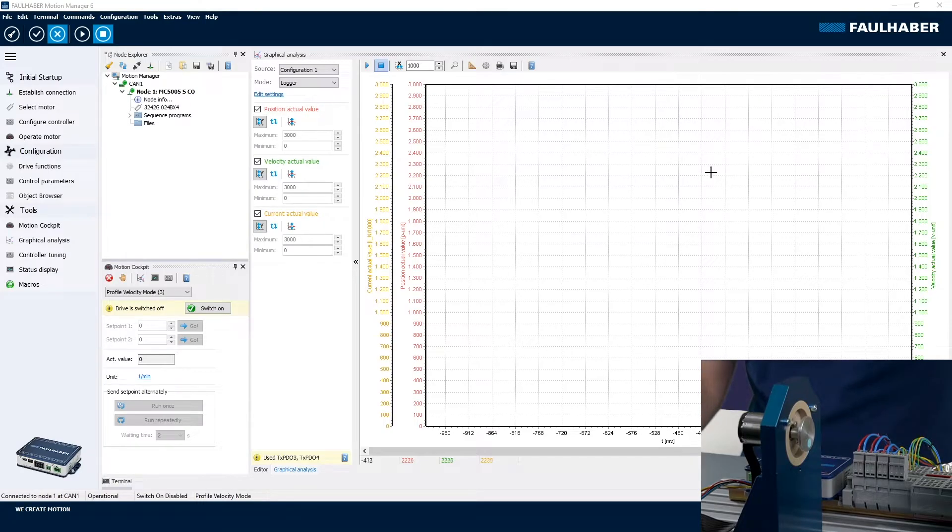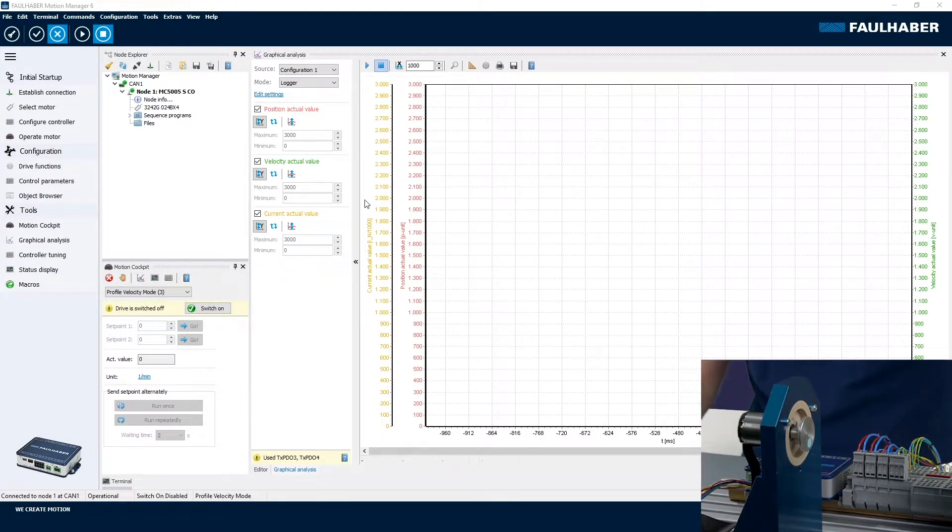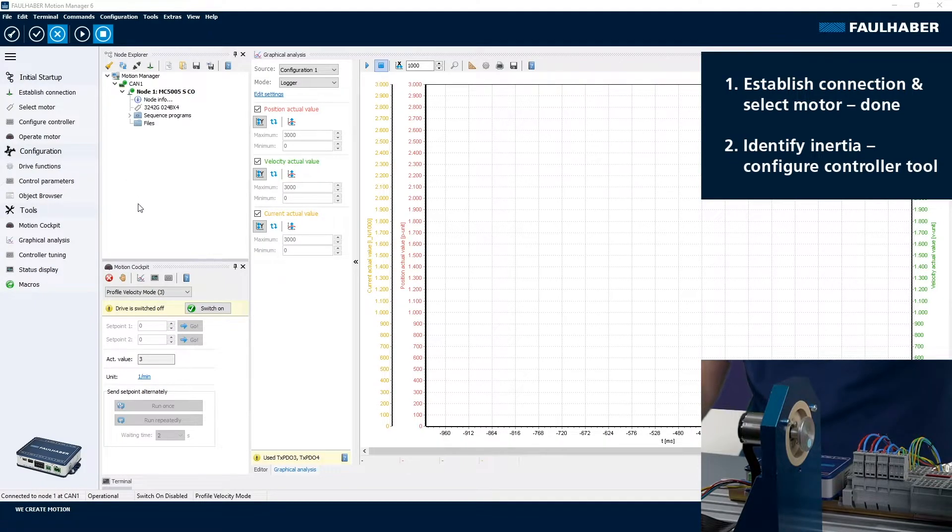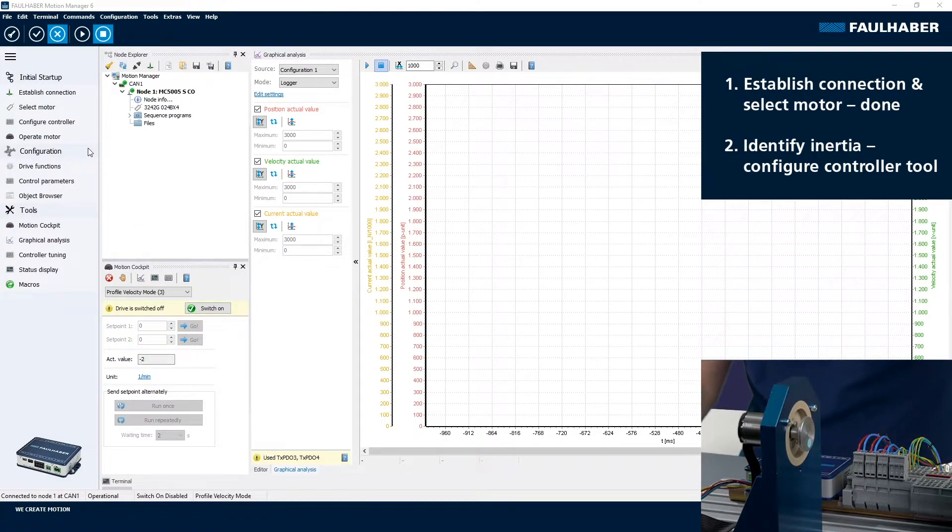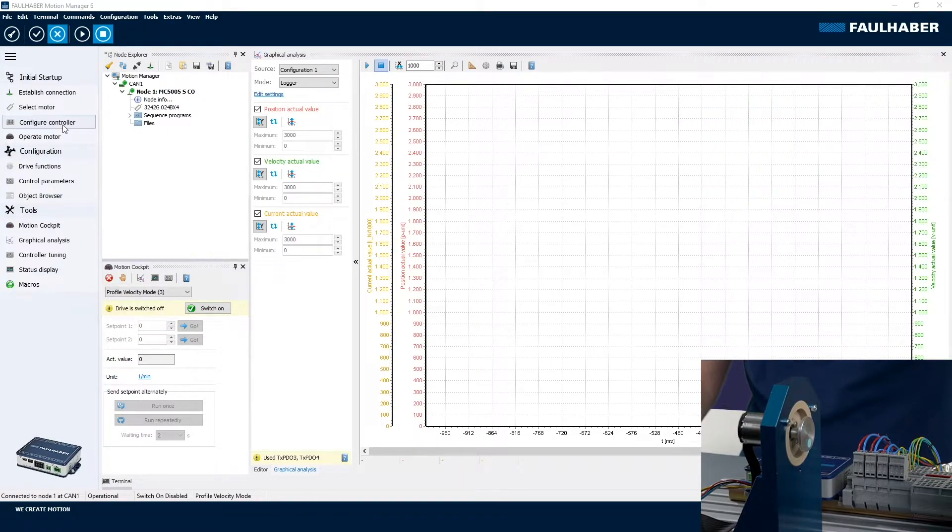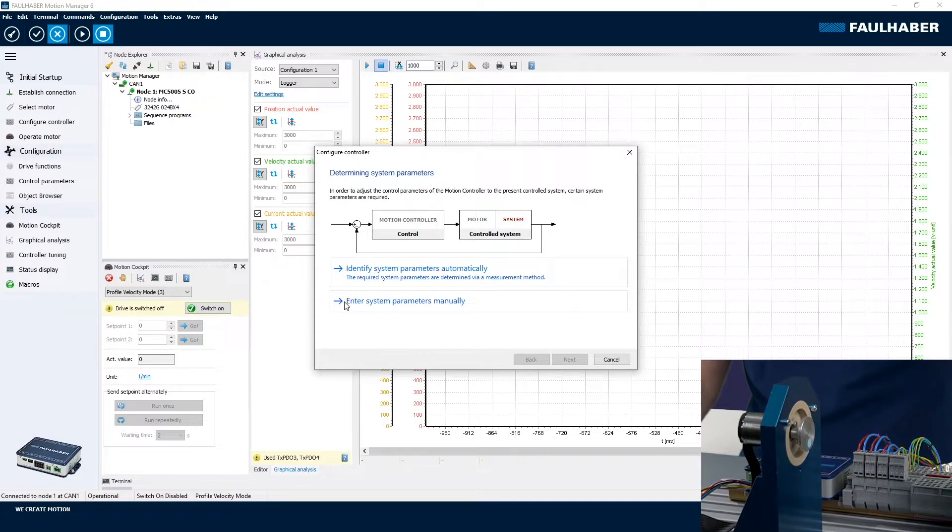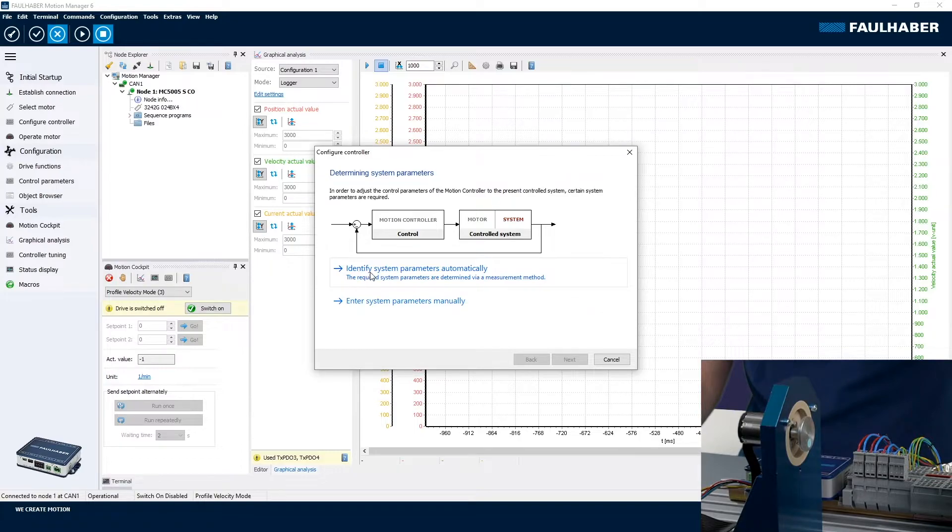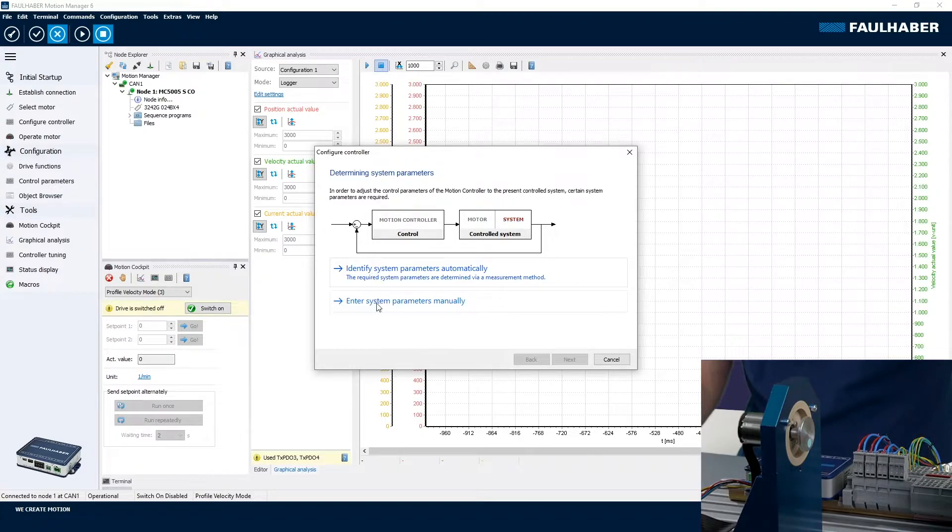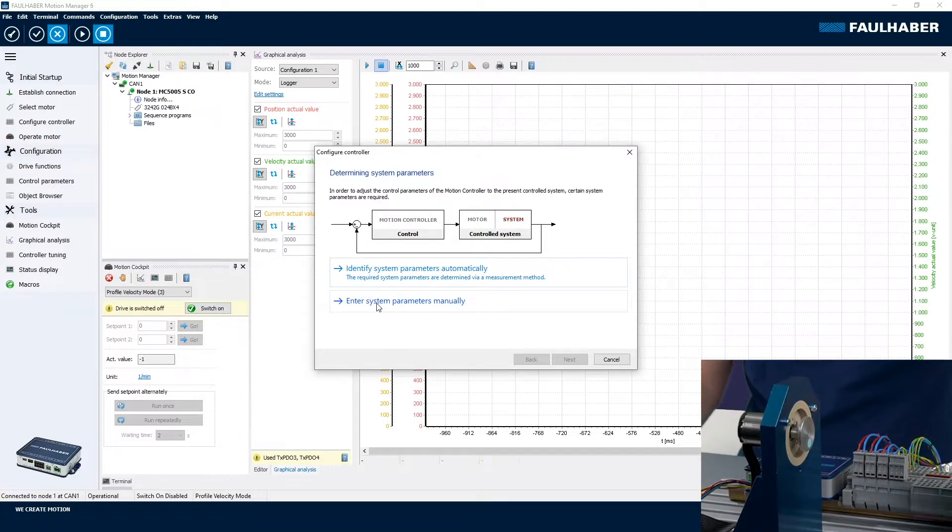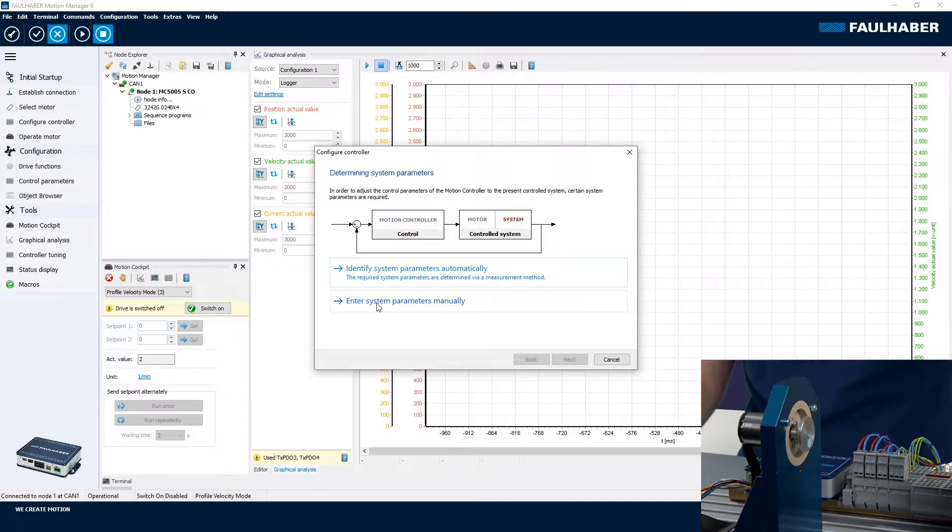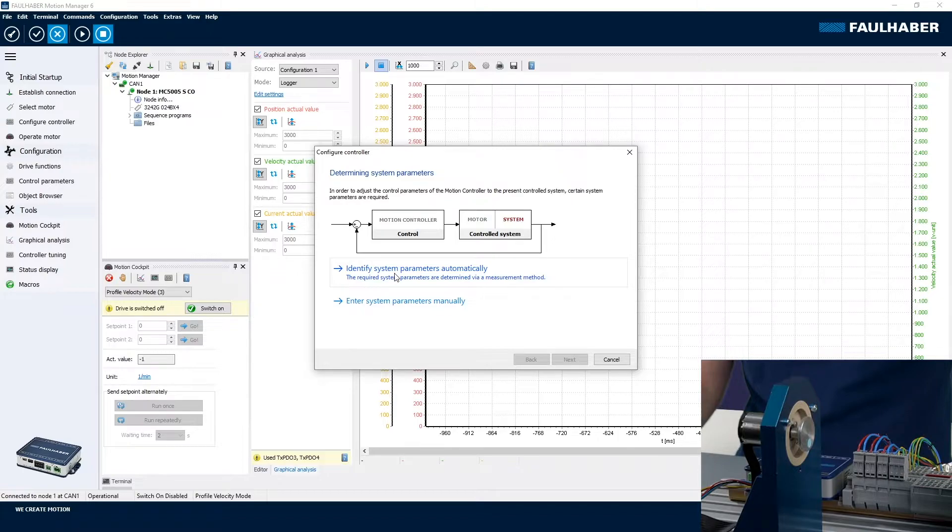So here is the view within the motion manager. You can see the motor is already configured and I can directly start with identification of inertia, and that's using the configure controller tool here. There are two ways we could either enter the value manually or we try identification. In many cases identification should work. If it doesn't work for you, please enter a rough estimate of the inertia manually because this is an important parameter for a preset of the complete control loop, speed and position loop. Otherwise you might have a hard time to find a stable control.